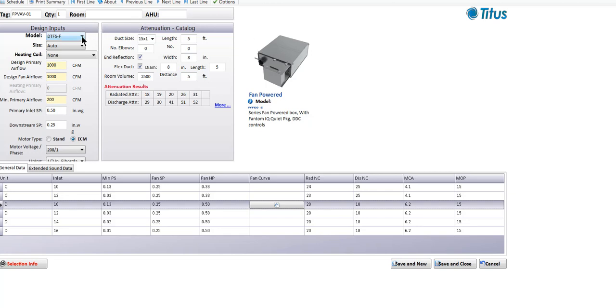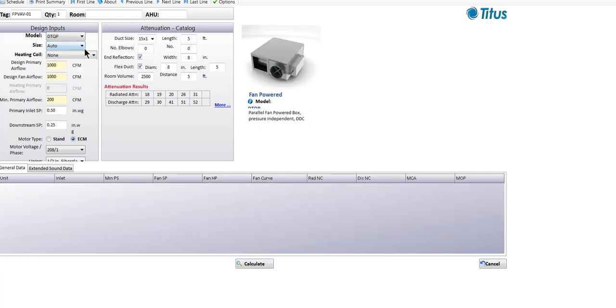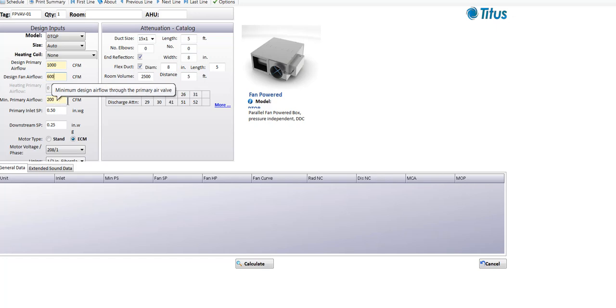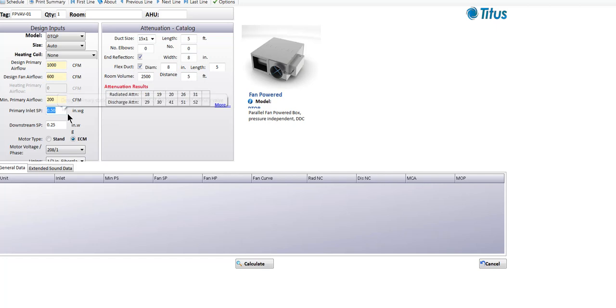Now I'm going to do a selection on a parallel fan box to give you some pointers on where people run into problems. If we had that same 1,000 CFM primary airflow as before: on a parallel fan box, the fan airflow shouldn't match the cooling design. I usually expect the fan airflow to be anywhere from 50 to 60% of the cooling design, because there's an old rule of thumb that says it takes twice as many CFM to cool a room as it does to heat it. So let's say we have a 600 CFM fan airflow with the same 200 CFM primary minimum airflow.